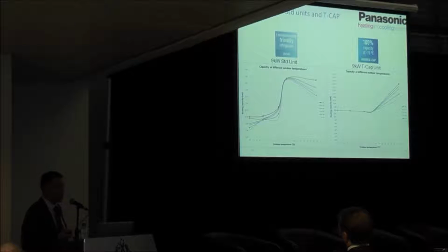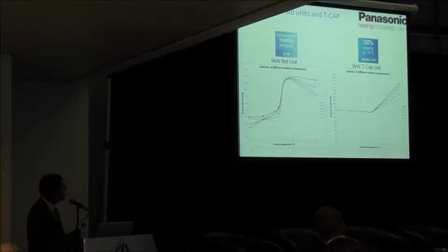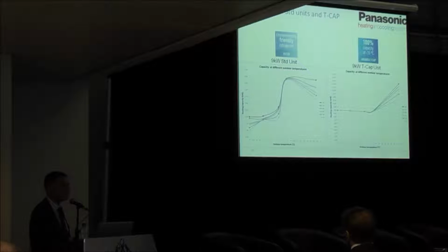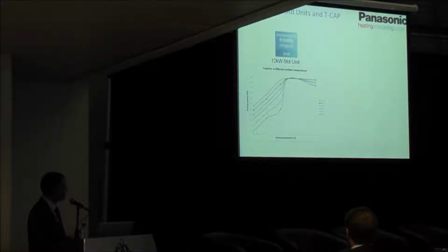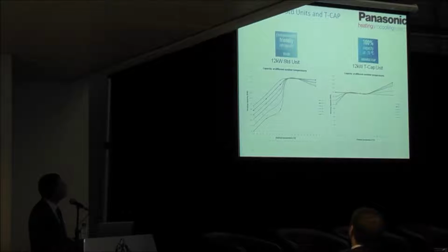But if we look at a total capacity unit or a TCAP unit, it's flat line. So no matter what the ambient, down to minus 15, we're still getting our 9 kilowatts thermal capacity. And in fact, if we go above 7 degrees C, we're actually getting a lot more. Whereas if you look at a standard unit, it actually decreases a little bit as the temperature rises. So you have to be certain in the design stage about what unit you want to go for. 12 kilowatt unit, standard, not quite as bad as the 9 kilowatt. And the 12 kilowatt TCAP unit, not quite as good as the 9 kilowatt TCAP. But that thermal drop off is only at higher water temperatures, and it's when the ambient gets to about -8 degrees C.